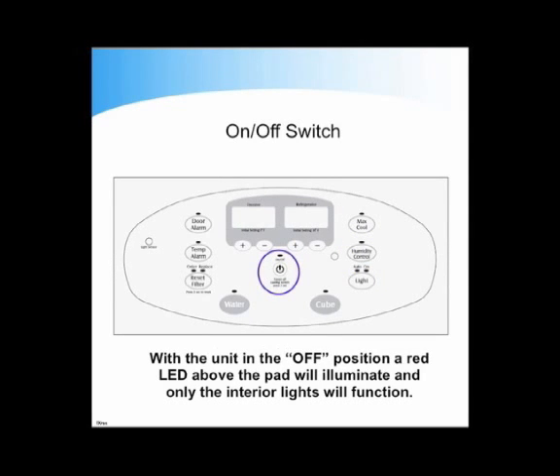With the unit in the off position, a red LED above the pad will illuminate and only the interior lights will function. The cooling on-off key will turn the cooling system off-on as described below. When turning the cooling system off, all keypad LEDs will turn off. The 7-segment LED display will turn off and a double beep will sound upon implementation. The red LED associated with the cooling on-off switch will turn on.